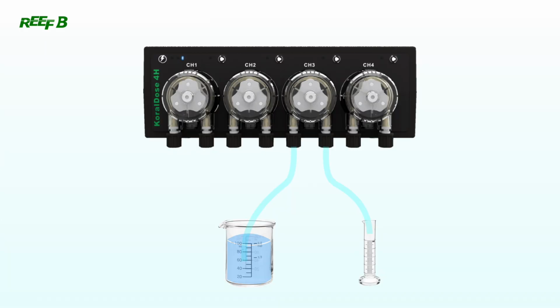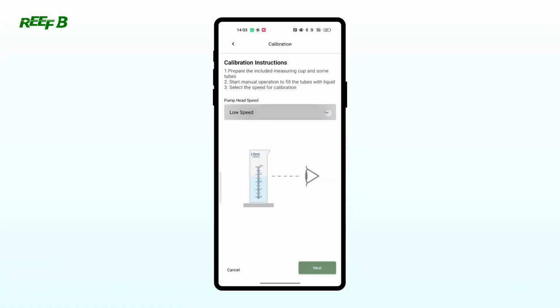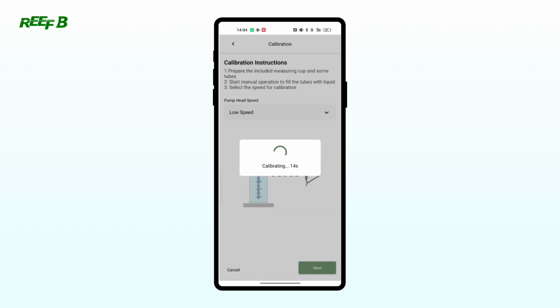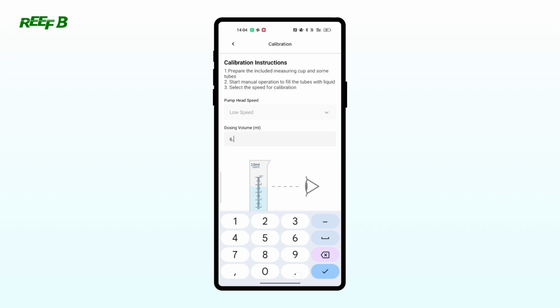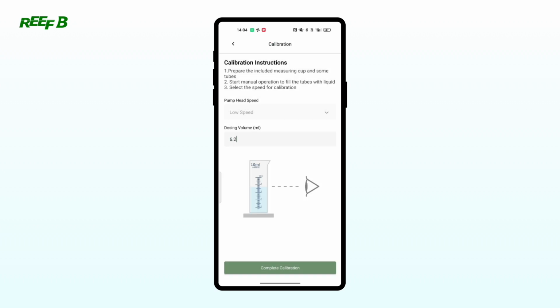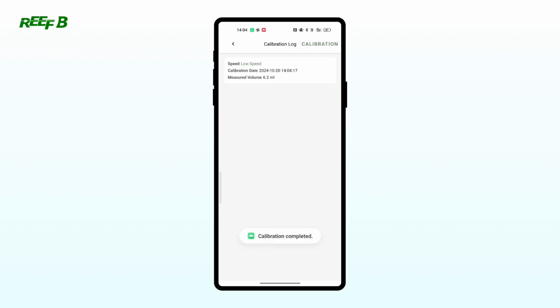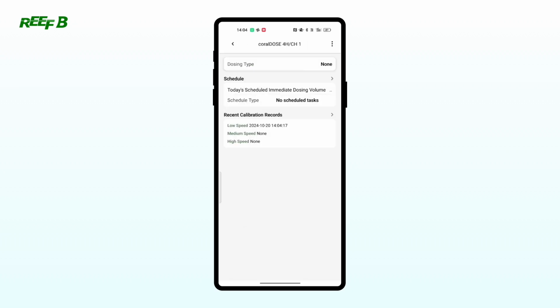Follow the instructions to prepare a measuring cylinder and install the silicone tubing. Remove any air from the silicone tubing and fill it with liquid. Select the speed and click the next icon to start calibration. Wait for 20 seconds. Observe the dosing volume and enter the measured value. Finally, click Complete Calibration to finish the process. The latest calibration information will be displayed on the pump head settings page.